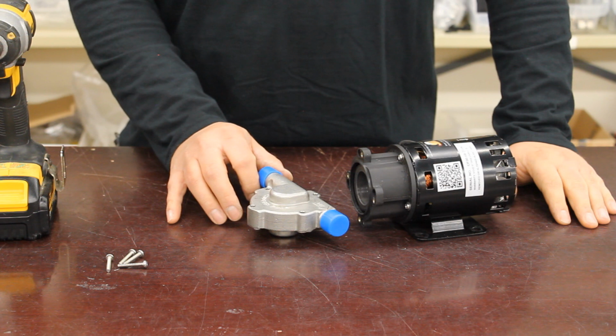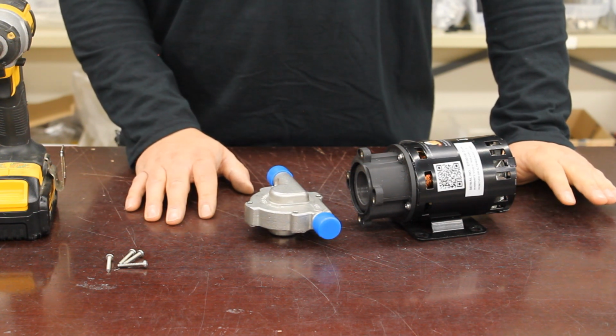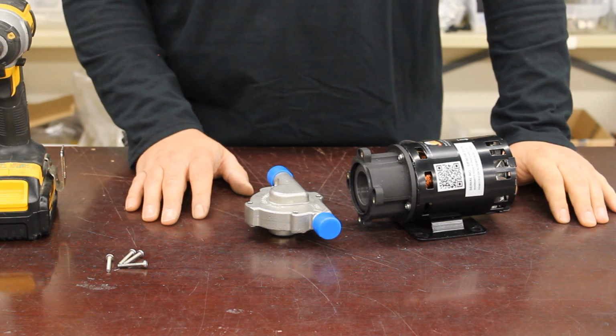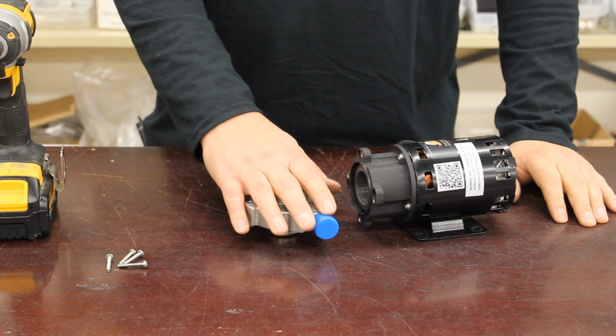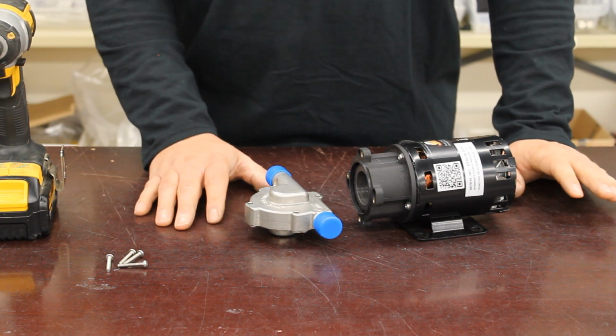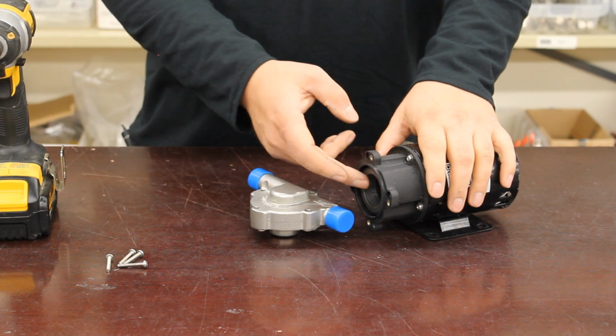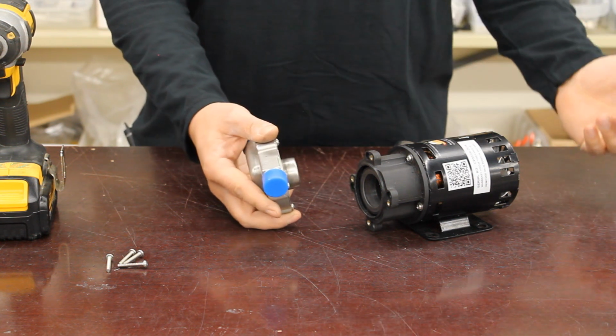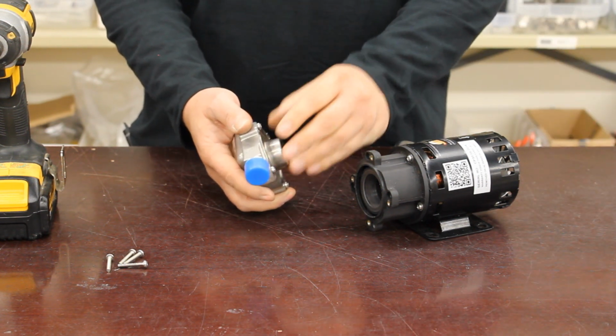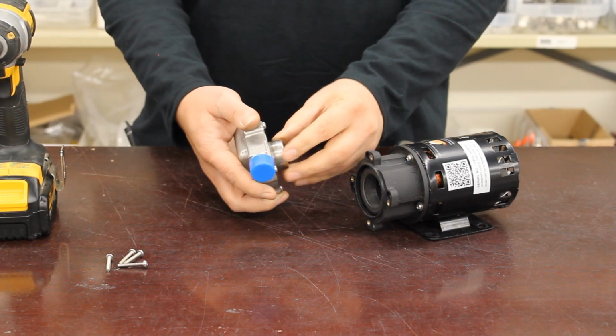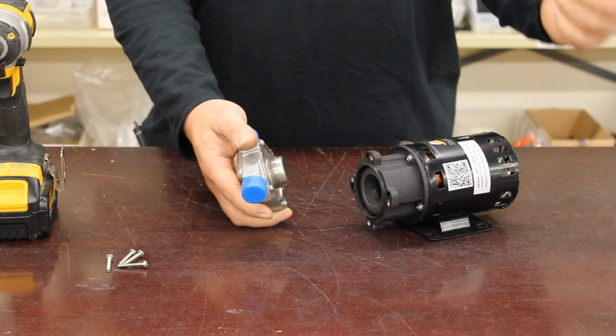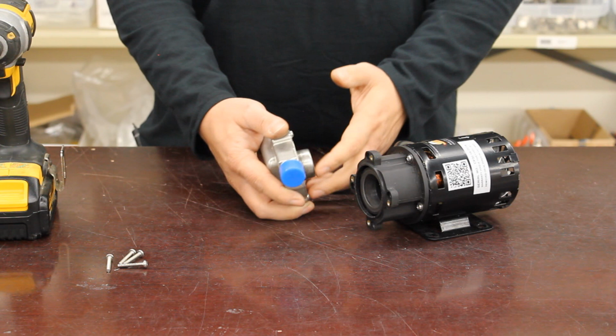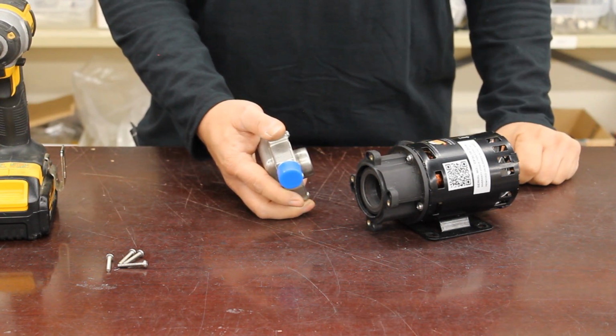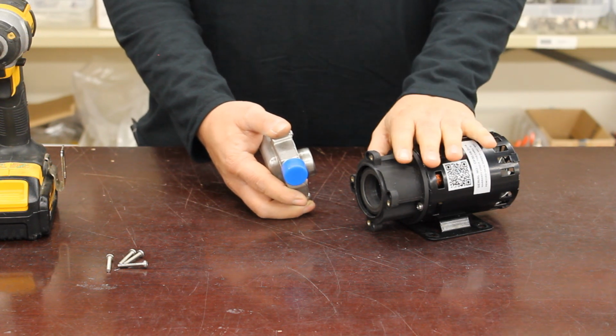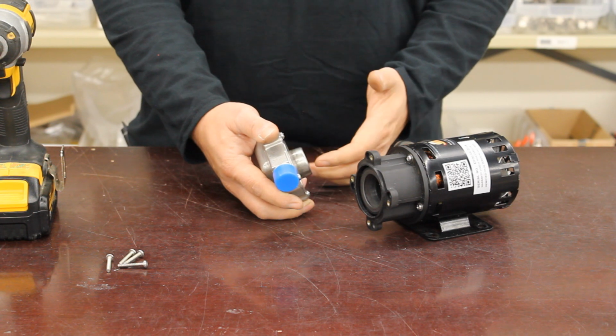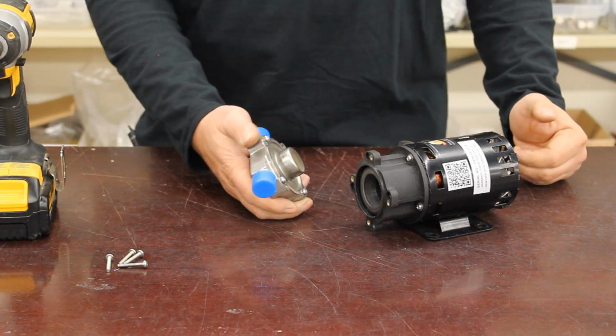Now, there are certain cases where customers will report that the pump works fine when the liquid going through it is cold or in the very beginning of brew day, but then as the brew day progresses and everything gets hot, that's when problems arise. Now, it stands to reason that if there had been any mechanical interference between the cup magnet and this back cover plate, it would be less of a problem when everything is cold, because everything shrinks a little bit when it's cold, and then as it heats up, the clearance between here and the cup magnet becomes less and less. So perhaps there is no problem, or I should say the problem is less when the head is cold, but gets worse as it warms up. Again, the remedy is exactly the same, but I just want to make sure that people are aware that sometimes the temperature just exacerbates the problem that already exists when it's cold, so it still needs to be remedied.